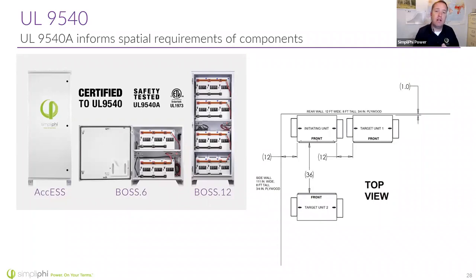You don't pass or fail. There can be an inconclusive test, where a battery cell is heated into thermal runaway but doesn't propagate to an adjacent cell—that's an invalid test. But when a heated cell did create propagation to an unheated cell, that was a valid test, still with no pass or fail. What the 9540A does is dictate what may be necessary to prevent a house from burning down, which is what's called out in UL 9540.